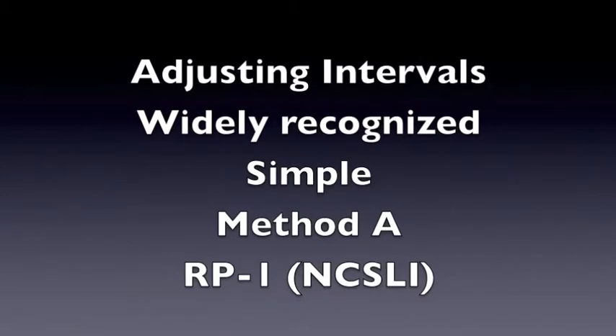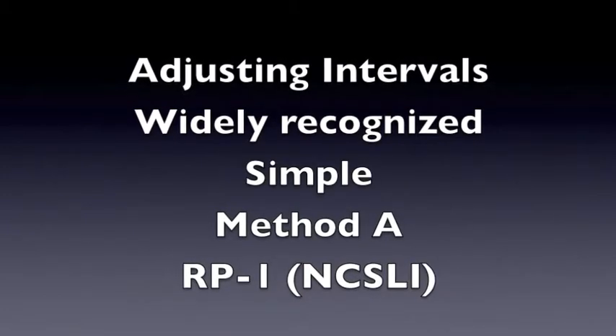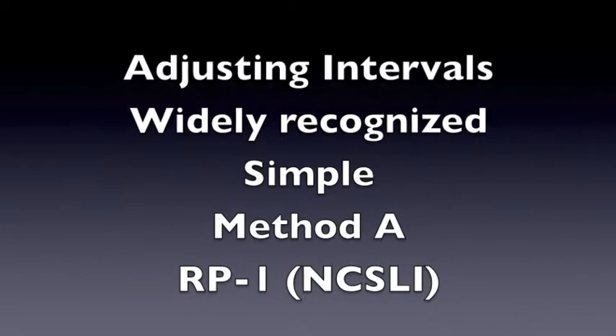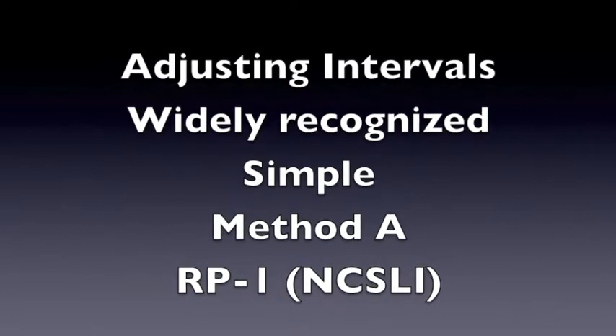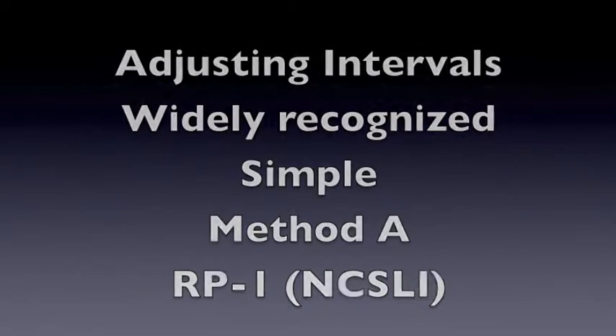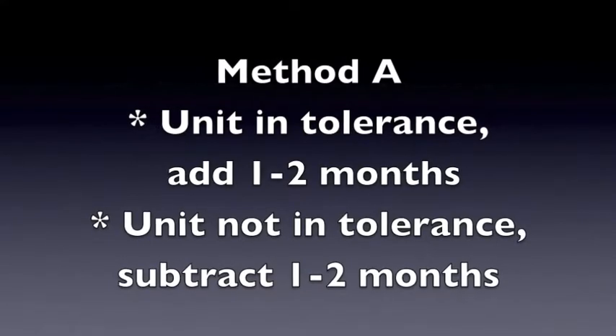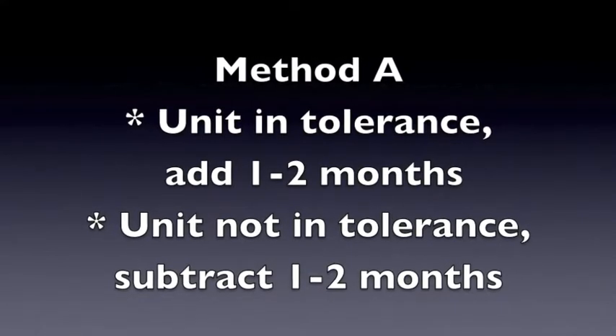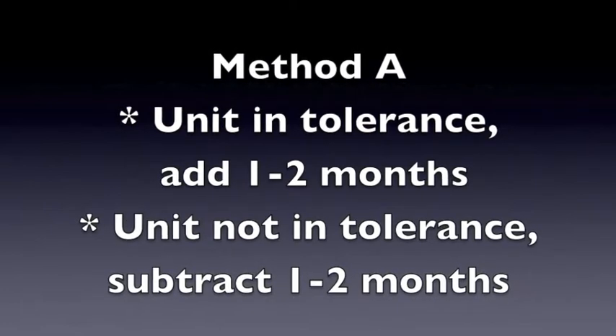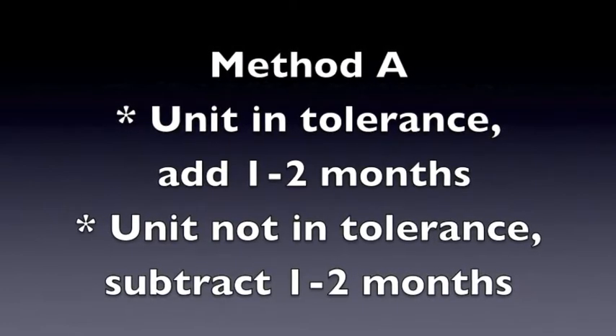Our final topic will be a simple method of adjusting intervals using Method A, a widely recognized method from Recommended Practice 1 from the National Conference of Standards Laboratories International. For Method A adjustment, if the unit is in tolerance after calibration, add one to two months. If the unit is not in tolerance, subtract one to two months from the calibration interval.